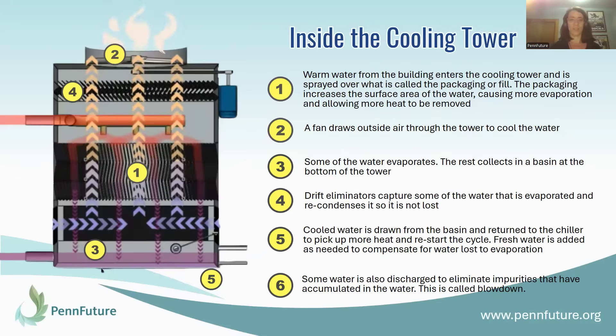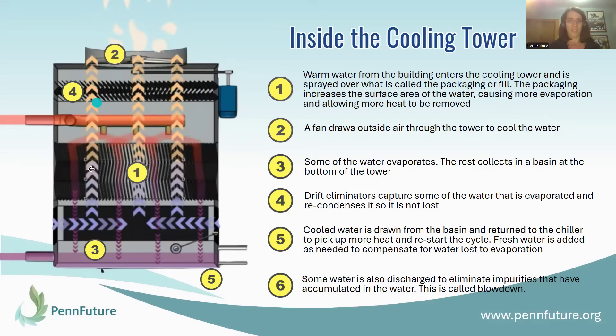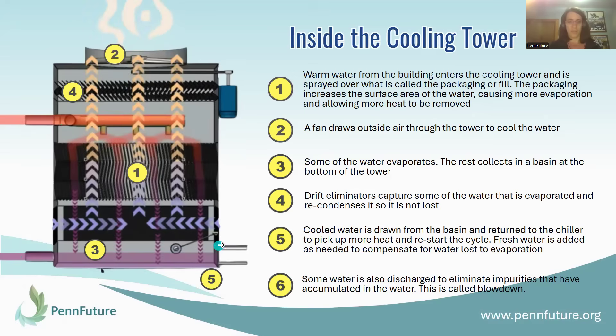Outside the building we have the cooling tower. That warm water gets pumped into the cooling tower and is sprayed out over what is called the packing or fill, which increases the surface area of the water and enables it to cool more efficiently. Fans inside the cooling tower draw outside air across this fill, causing some of the water to evaporate, and the rest gets cooled down and flows to the bottom. The cooling tower may also have drift eliminators that capture some of the evaporating water, recondense it, and let it flow back down so it's not lost. The cooled water then re-enters the pipe and goes back into the building to the chiller to collect more heat.